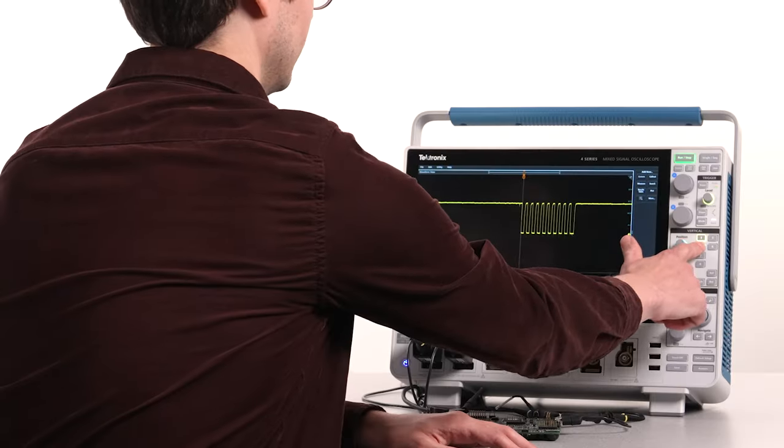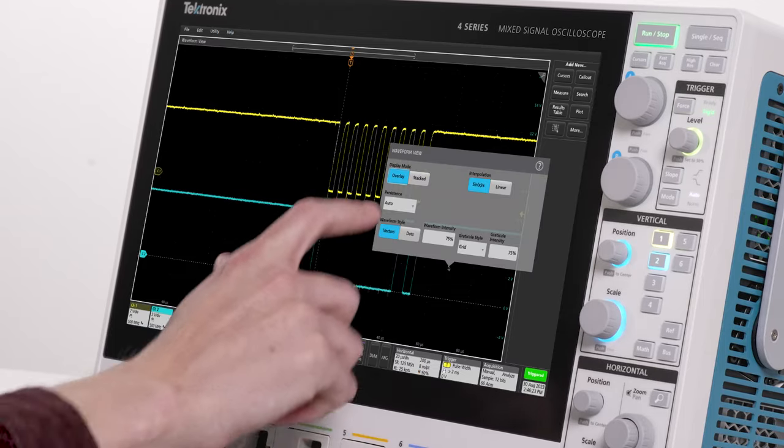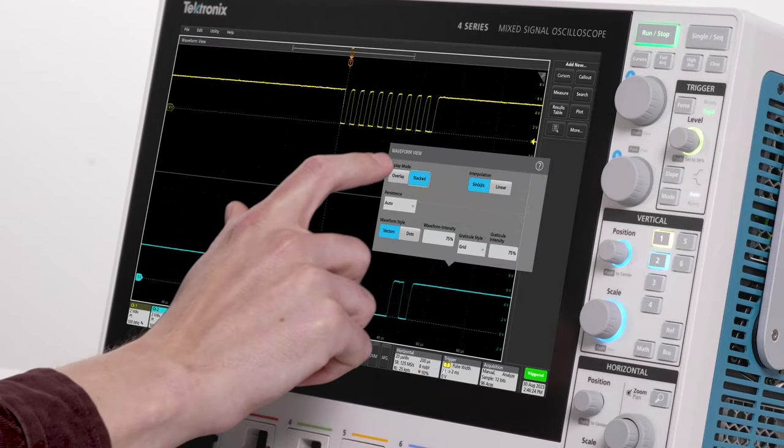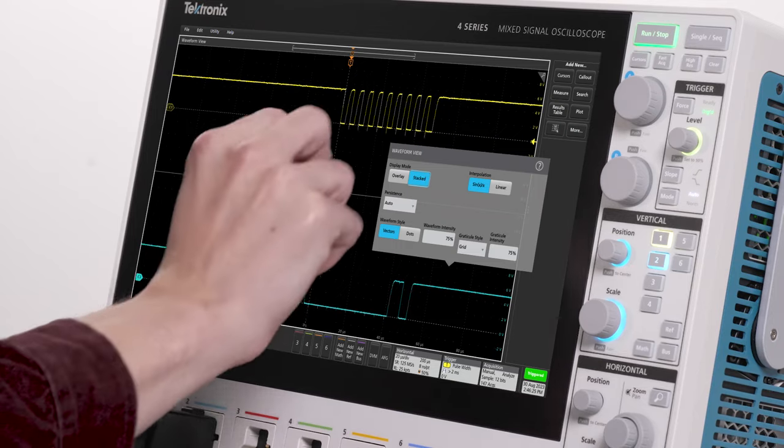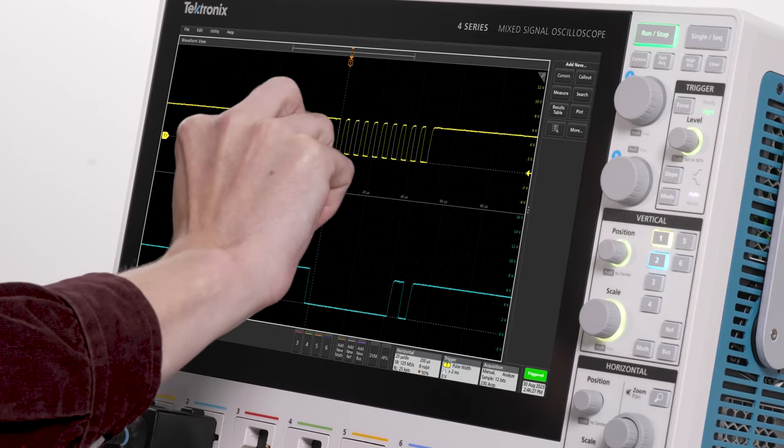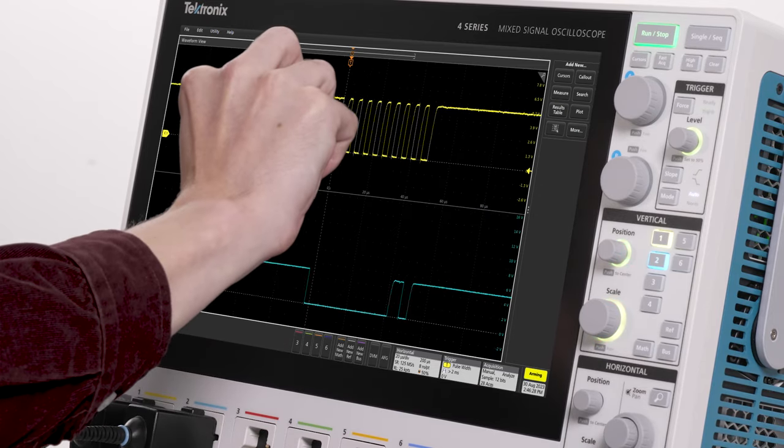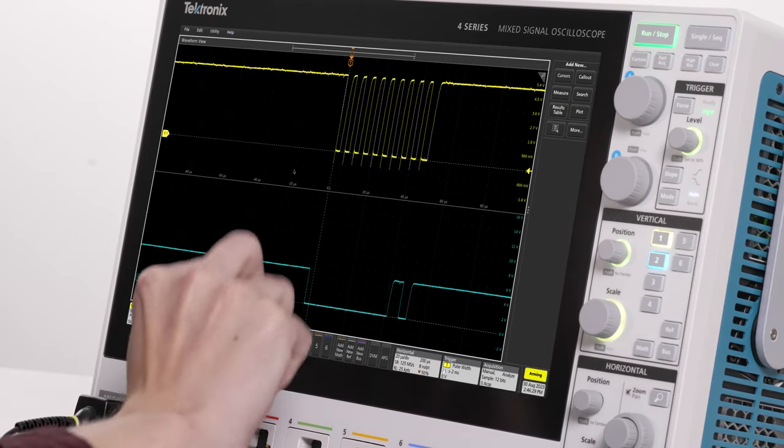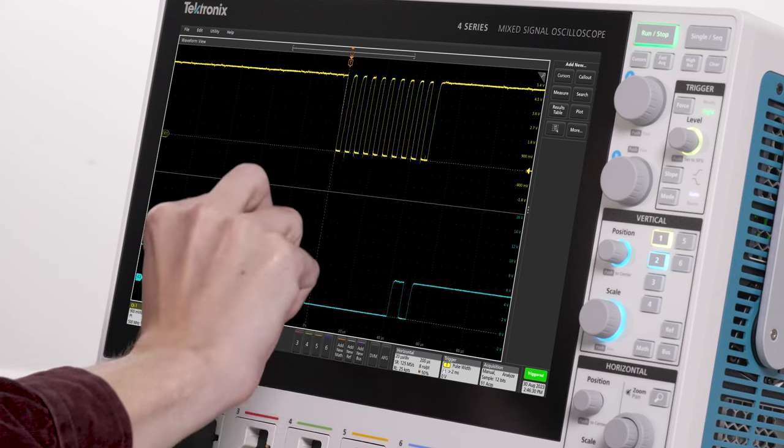Now let's turn on another channel and change the display to stacked mode. In this mode, each waveform is visually separated from the others, yet it's still able to use the full range of the 12-bit A to Ds.